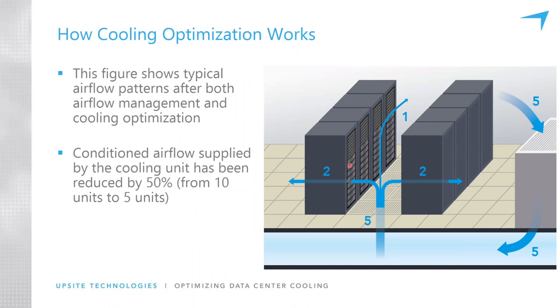And they are independent. If you turned off all the cooling units in a computer room, all the fans in the IT equipment, assuming they're all on UPS, of course, will continue to operate and will continue to move 4 units of air through all the IT equipment. Totally independent of the amount of air moving through the cooling units. And what if you added 5 more cooling units in this room? There would still only be 4 units of air moving through this IT equipment. So the amount of air moving through the IT equipment and the amount of air moving through the cooling units is independent and separate. And we want to create an environment where we can match those two as closely as possible.